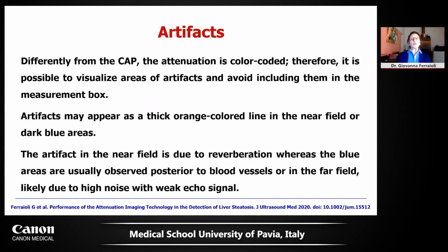Also, having a color-coded attenuation, we may look also at artifacts and not include them in the measurement box. This is very different from CAP and helps a lot in choosing the area where to perform the measurement.